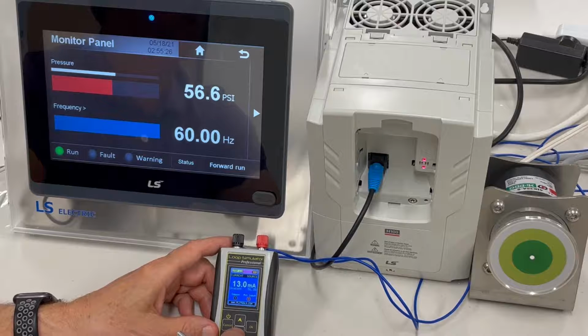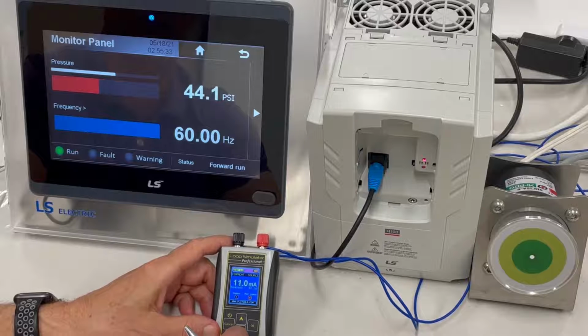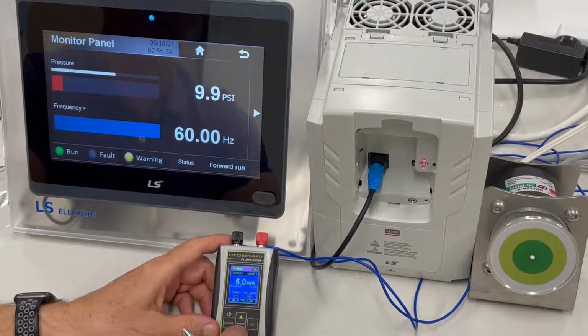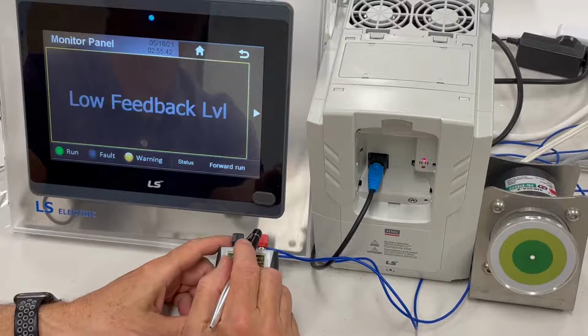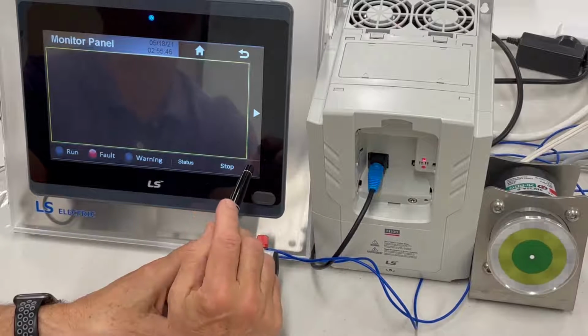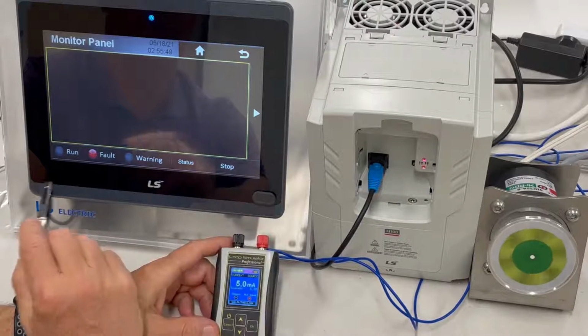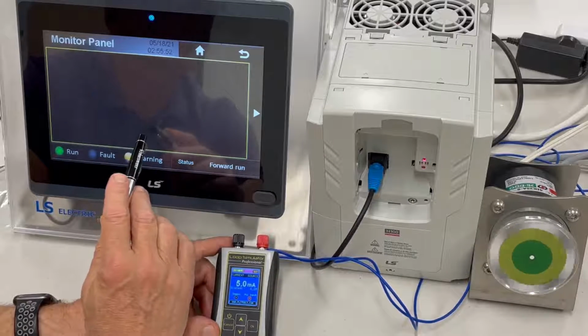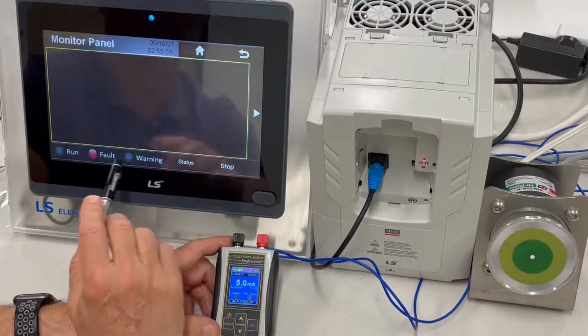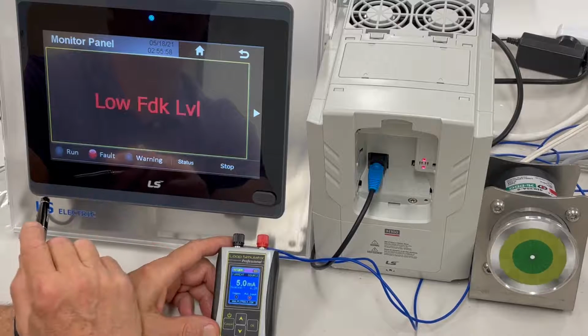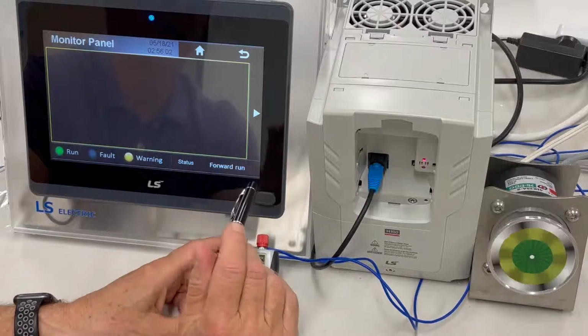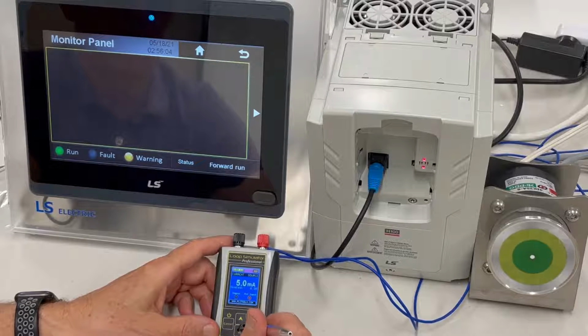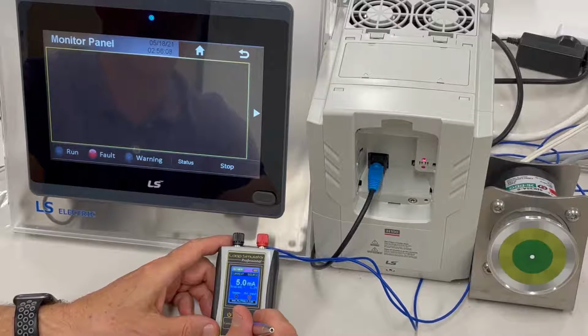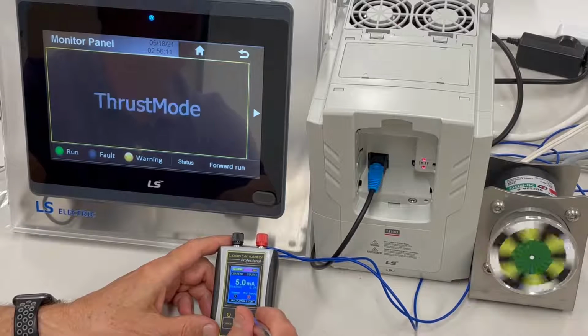Now, if we wanted to simulate a transducer wire break or some sort of failure of the 4 to 20 milliamp pressure transducer, all we have to do is get down below 6 milliamps or under the 10 PSI level, and we notice we have a low feedback level. The drive is going to stop the motor. So we have a flashing warning where it was our thrust mode protection as always. Configurable if you choose to use it, if you need it. And we're going back once again. We're having another low feedback moment, and it's tripping out again. So then it will try 3 times before it stops.